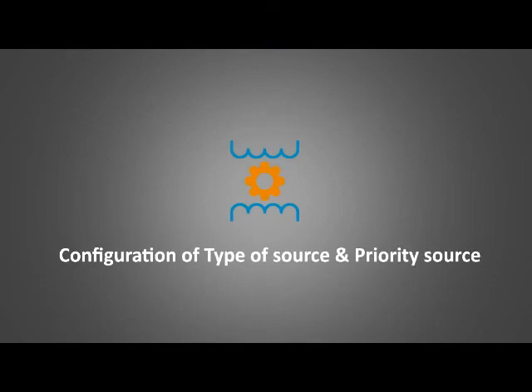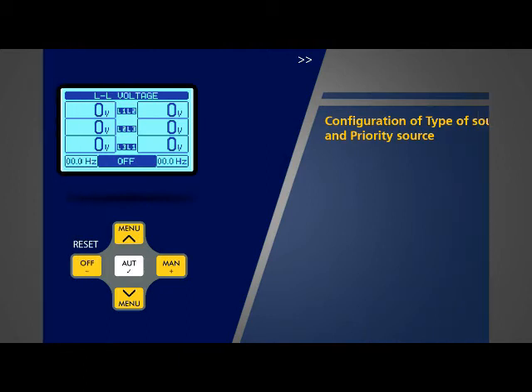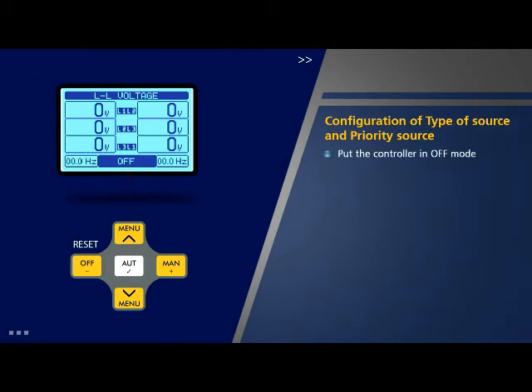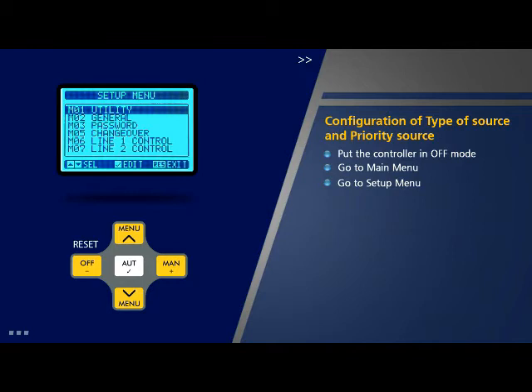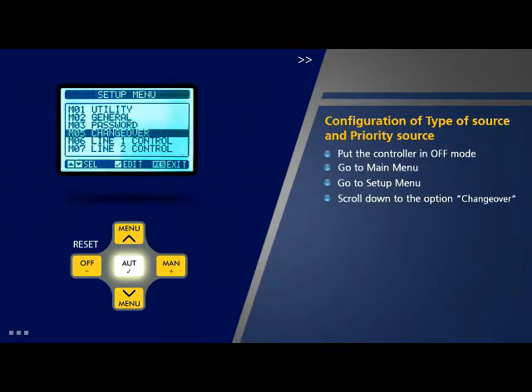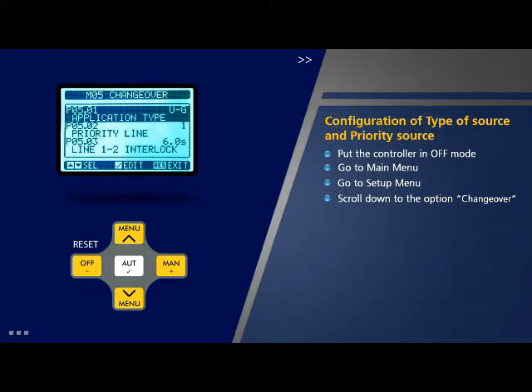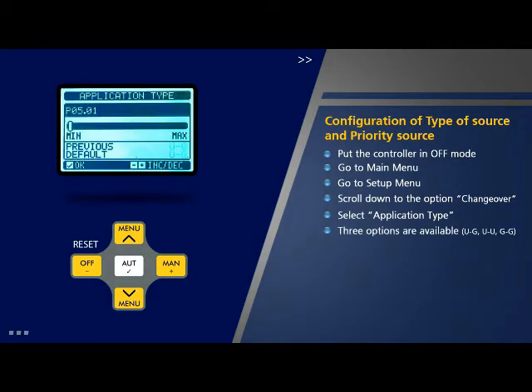Configuration of type of source and priority source: The method for configuration of the type of source — utility or DG — is as follows. Put the controller in off mode, go to main menu, scroll to setup menu and press OK. Select option 5 which is 'Change Over' and press OK. The change over page will appear. Select the parameter 'Application Type' and press OK. Three options are available: UG (utility-generator), UU (utility-utility), and GG (generator-generator). Select an option, for example UG, and press OK.